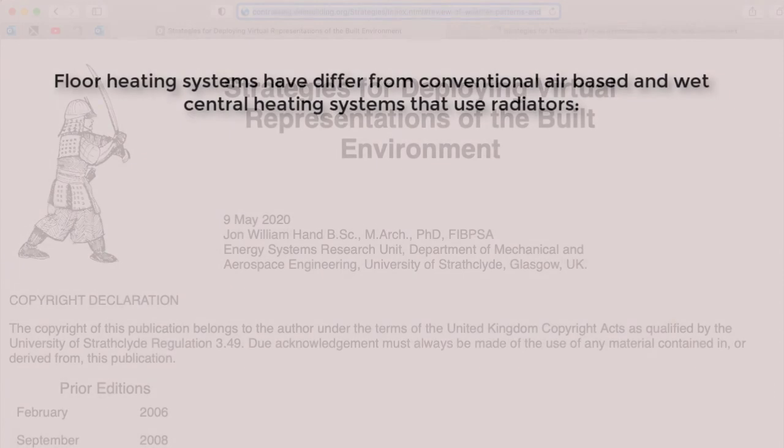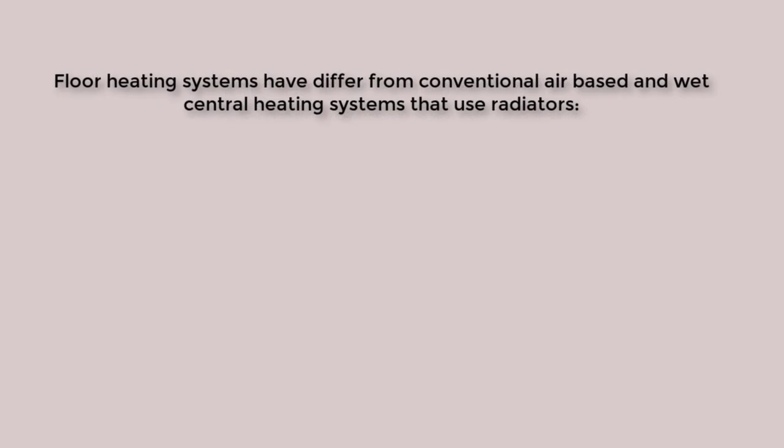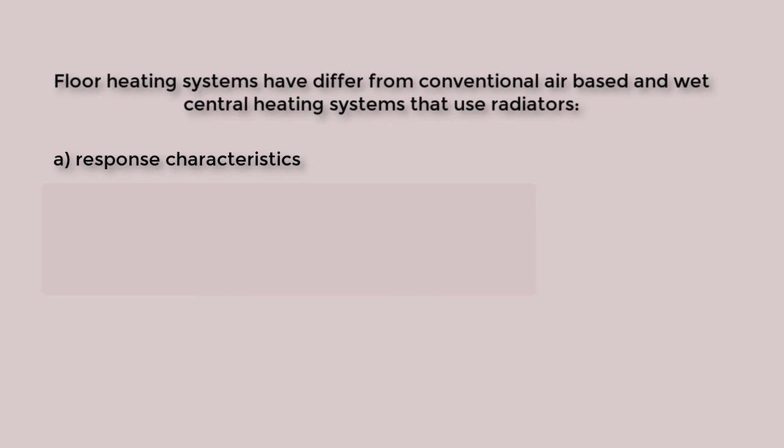Floor heating systems differ from conventional air-based and wet central heating systems that use radiators. Firstly, they have a slow response to control signals. It may only take a few moments for an air-based system to respond to a control change. Radiators may take maybe 15 minutes to come up to temperature and then might take a half hour to drift back to room ambient temperature when the signal turns off. But the timings associated with floor heating are greater still.